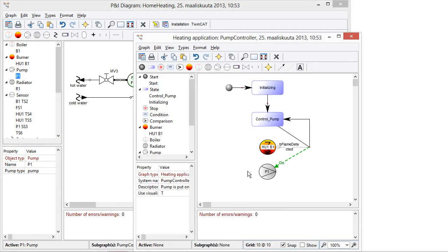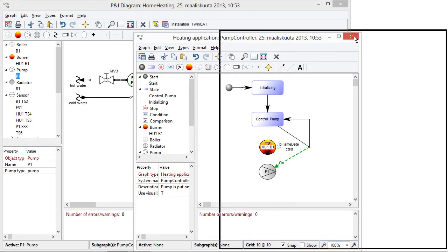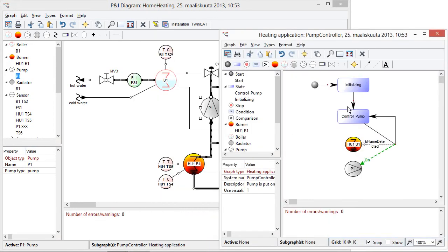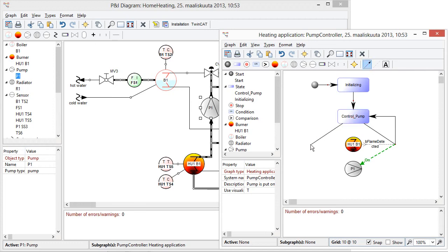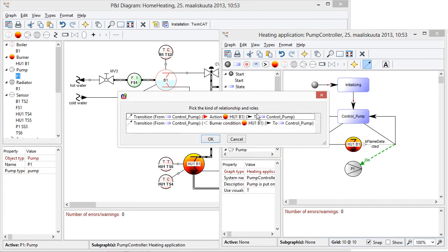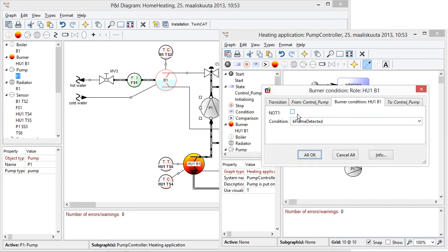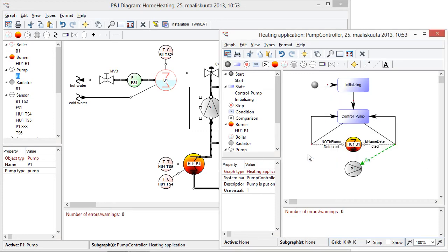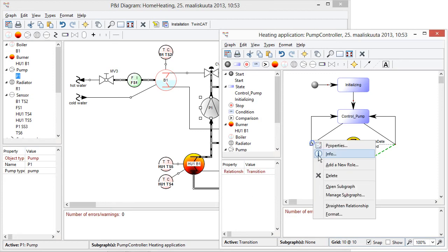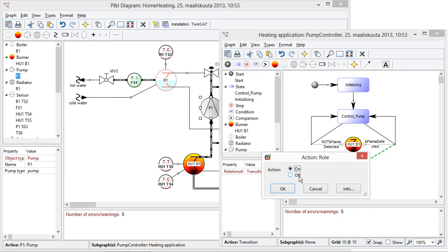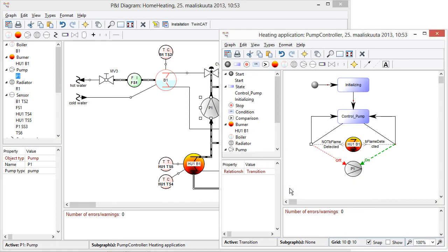If you look for instance the pump behavior. So here you can see a state machine describing how the pumps are controlled. So the system is initialized and we call the control pump. If flame is detected we put the pump on. We could also add here another condition with a transition that if flame is not detected. So here you can see again domain concepts what kind of things we ask from a burner. And if flame is not detected then we should put the pump off. So here you can see again domain concepts what kind of things we can do with the pump on and off.